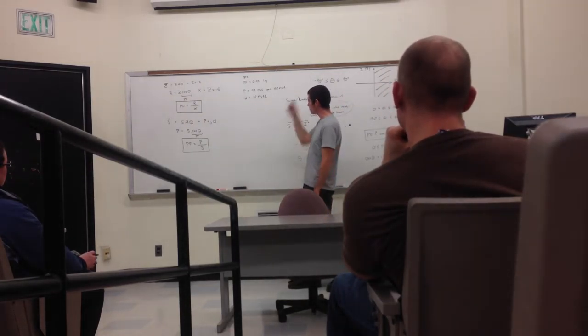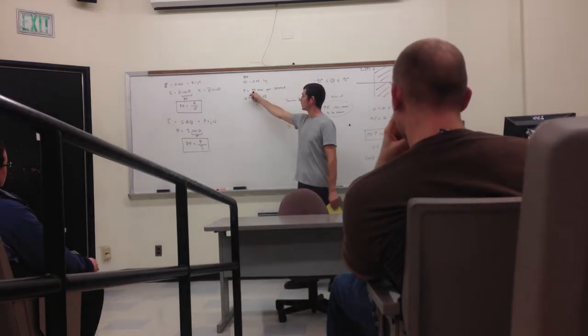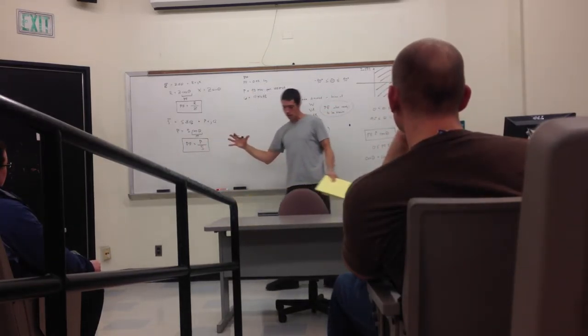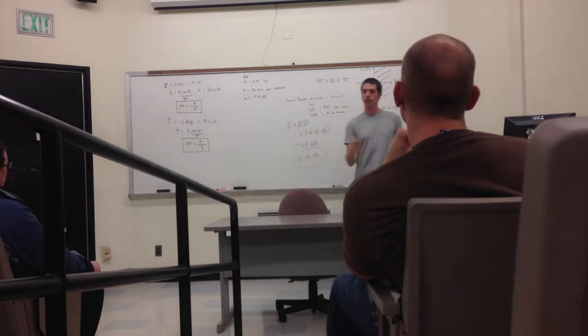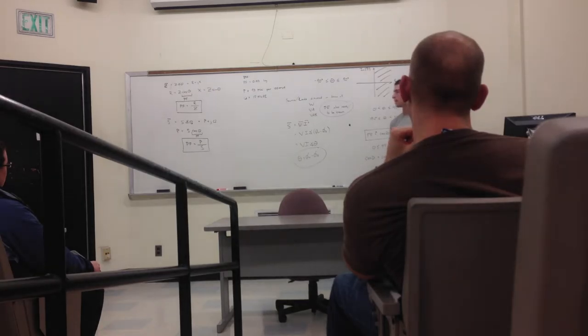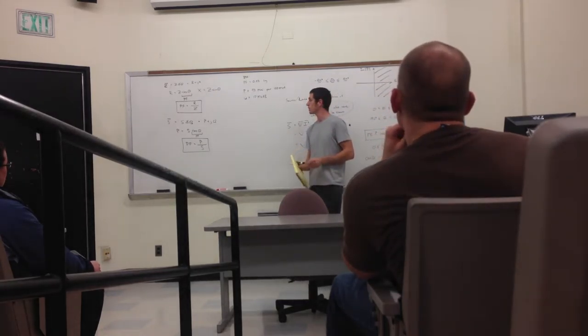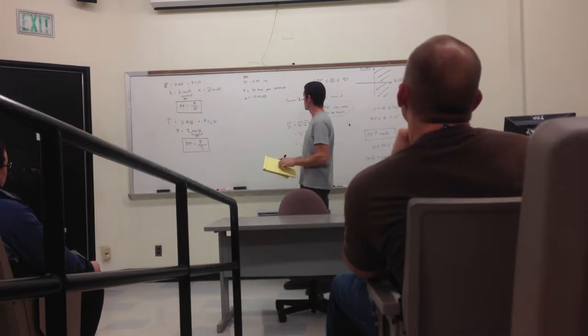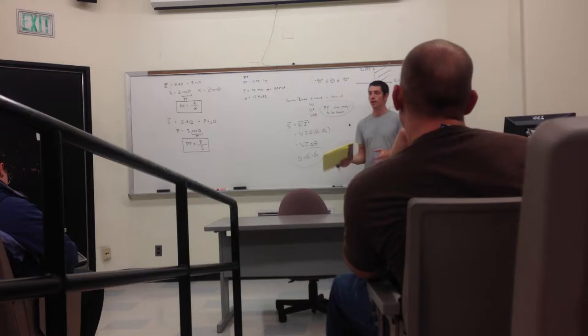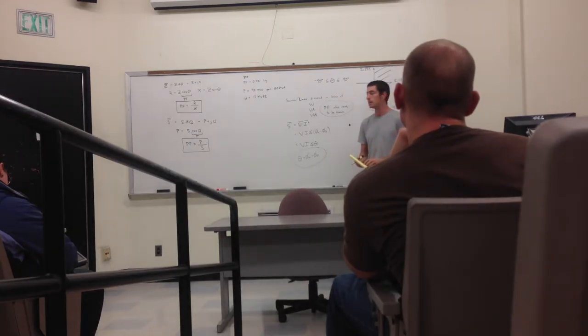So he still has a fair amount of VARs on there, but you're mostly looking at real power. It's really giving you a sense of how much of the capacity of a line is being used for real power. At 0.97, you're delivering a lot of real power. Typical loads are between 0.8 and 0.95, lagging typically.